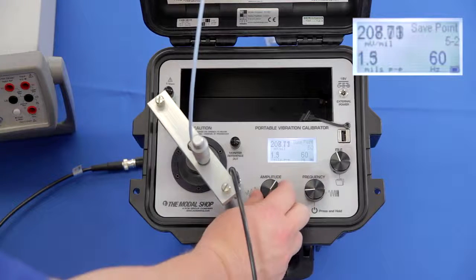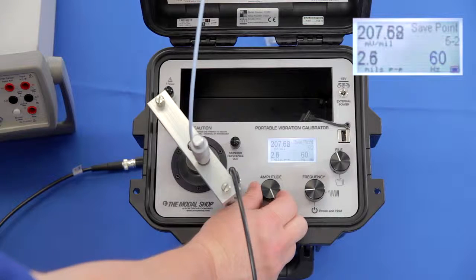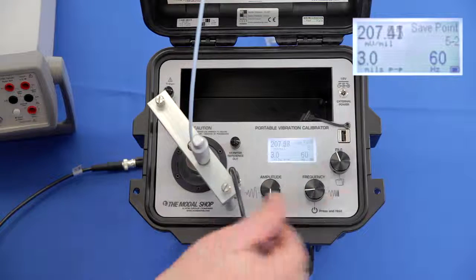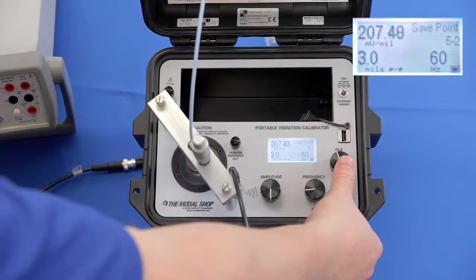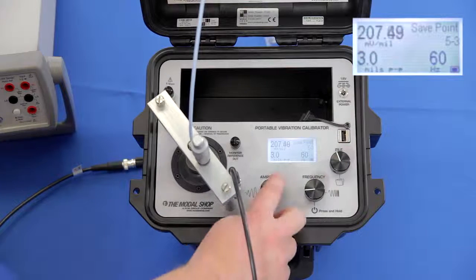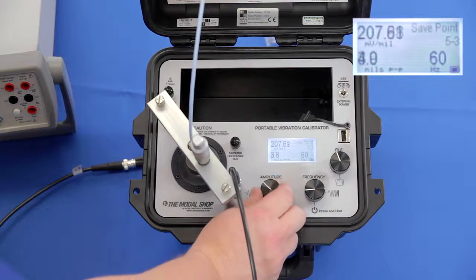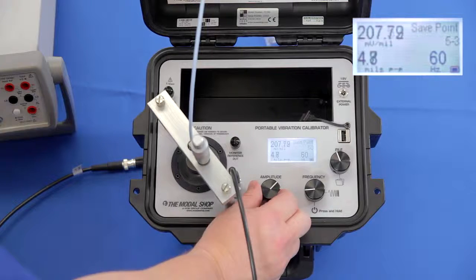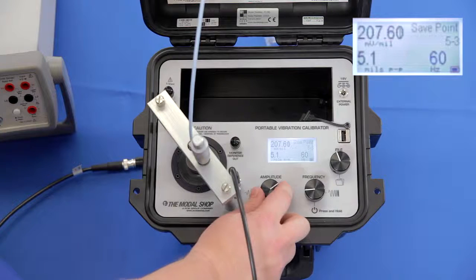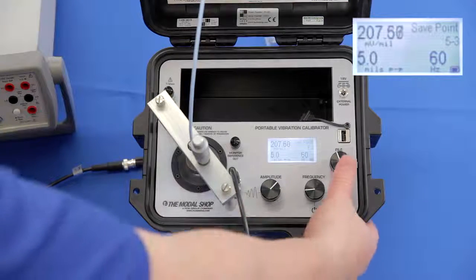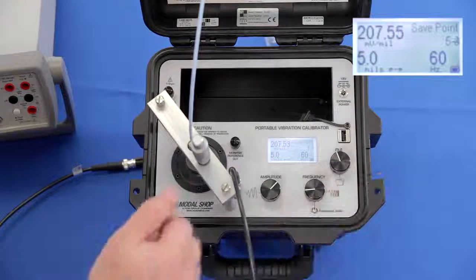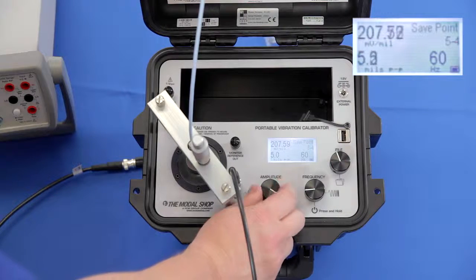Now I'm going to rotate up to 3 mils peak to peak and save another point. Sensitivity has remained at 207. Let's go to 5 mils peak to peak. Now if you weren't creating a calibration certificate and you had your proximity probe hooked up to the online system, at this point you'd be checking to see if your alert settings have tripped. Maybe the set point is set at 5 mils peak to peak or even lower.